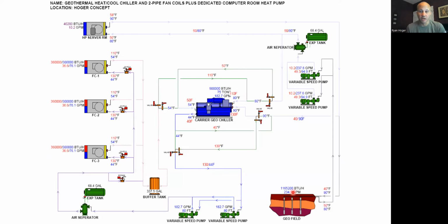This is a piping diagram that I did when we first started conceptualizing this at my office. This is from 2008, I think, is how long ago this was. Before that, we didn't really do this. And we don't do it a lot, honestly. It's a rarity, but you can do it. In this case, I have 3 fan coil air handlers on here. It could be 3, it could be 300, right? But from a drawing standpoint, you can't put everything on here. So I put 3 of them on here, and I only showed 1 chiller, but you could have 2 of them, and that's more likely as well. But this is just showing 1.